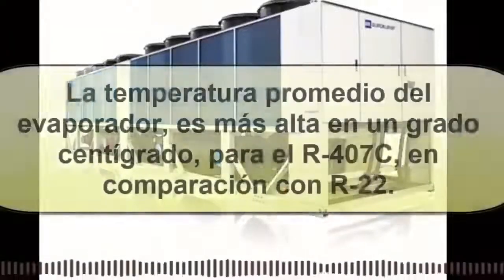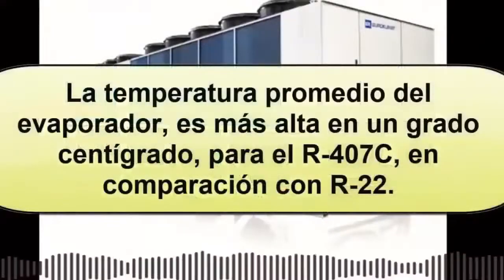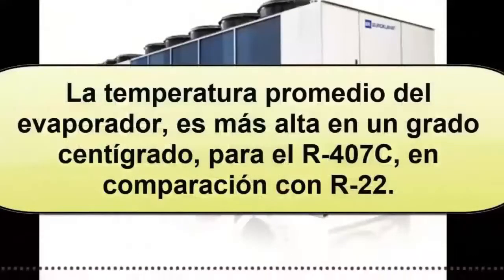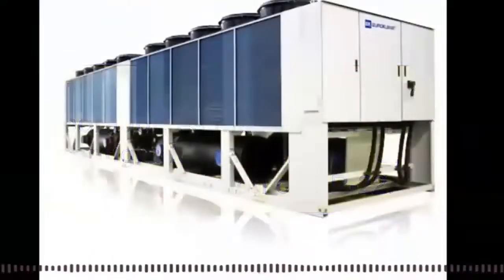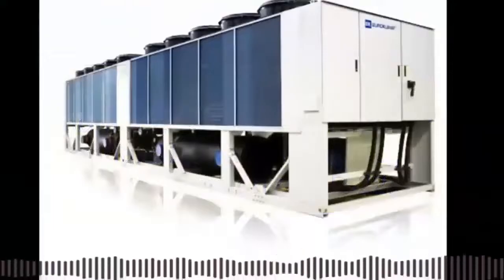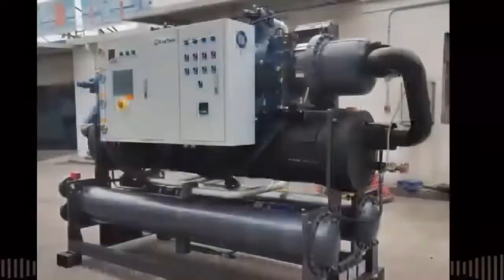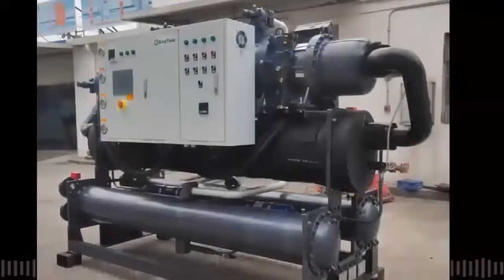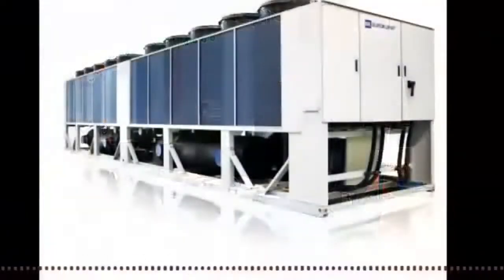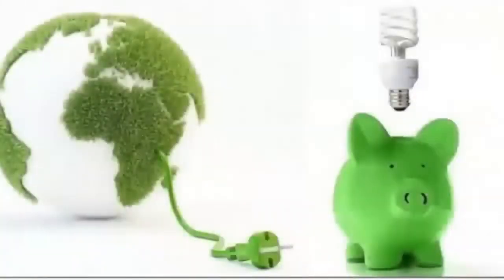The average evaporator temperature is 1 degree Celsius higher for R407C compared to R22. Cooling capacity is approximately 5% higher for R407C compared to R22. The energy efficiency index is about 0.5% higher for R407C than R22 on average.